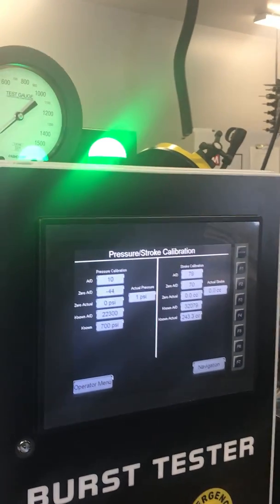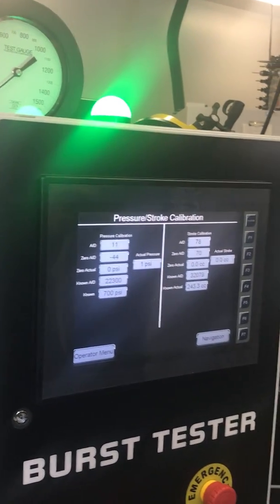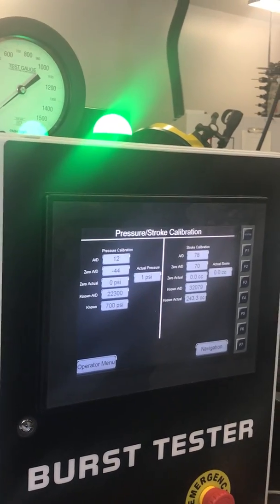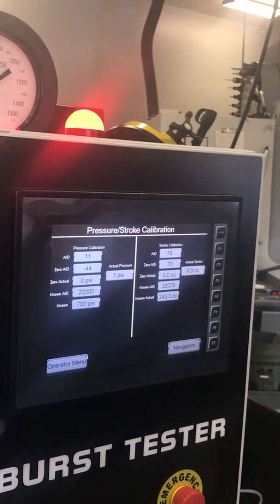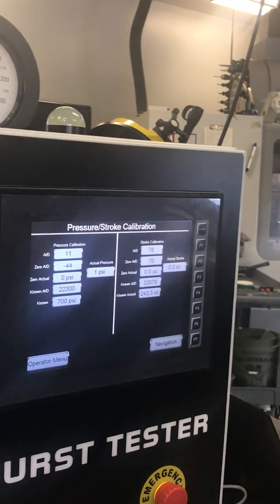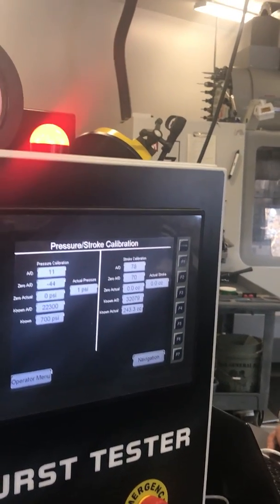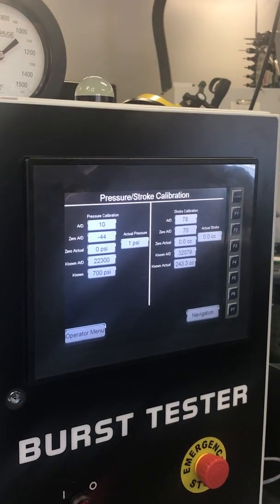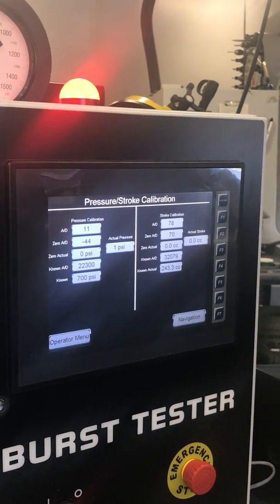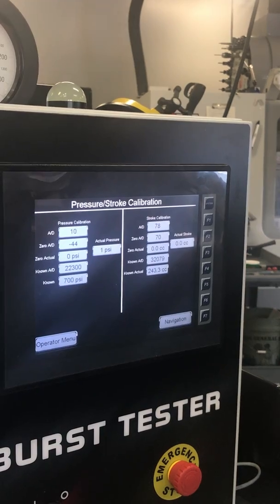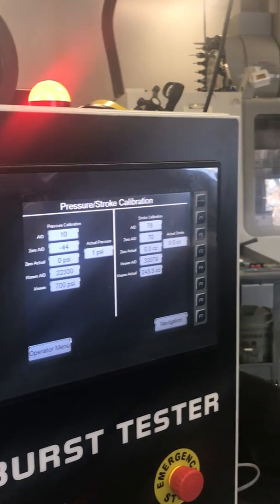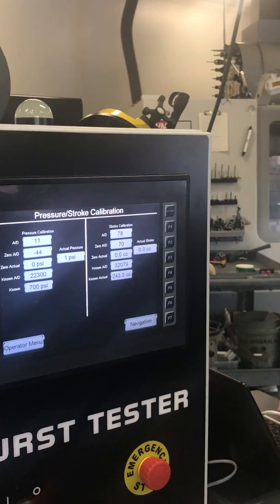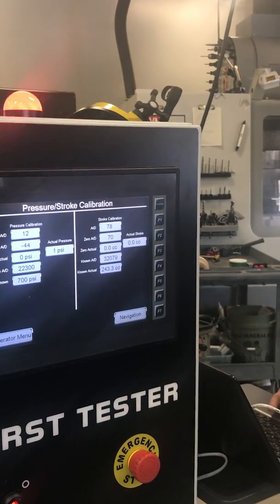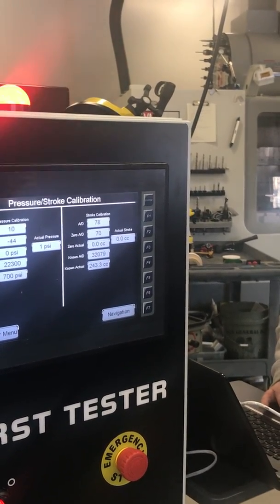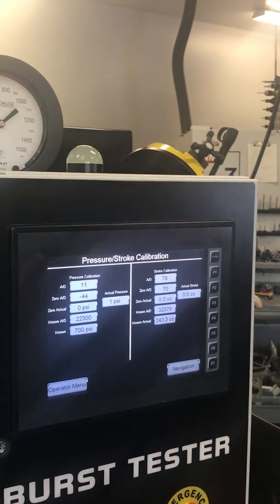It may be a phone call the first time you want to mess with it, I would guess. How often will we have to mess with it? Shouldn't have to. Once we're set up, this pressure transducer can handle shock and much higher pressures. It's never going to see that. So it should go and go and go. Perfect. I would like to say that it'll last that way forever, but as a practical matter, somebody from your quality department needs to do a systematic check and see that the standards are being met. Correct. So that's probably when that gauge comes out, and then you do a 0 and span and see that it's right. I don't know if it's once a week or once every 6 months or something.